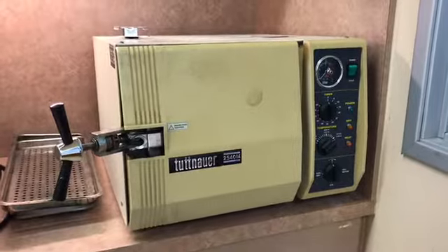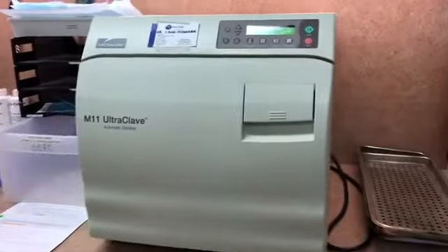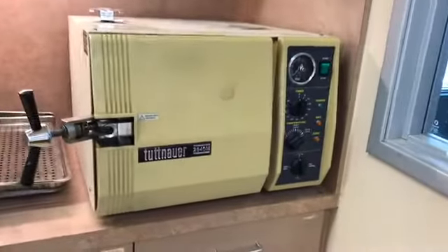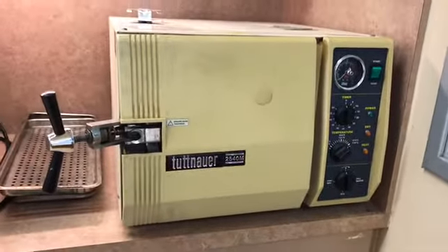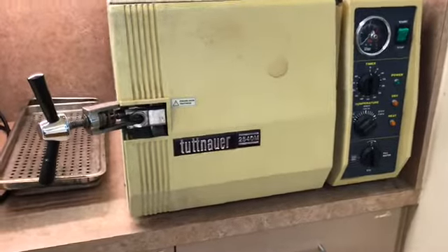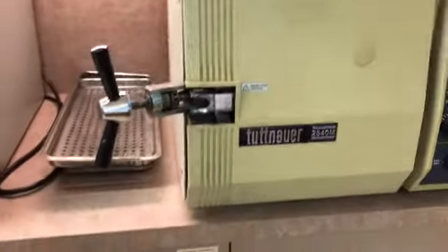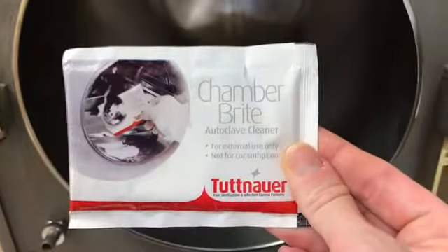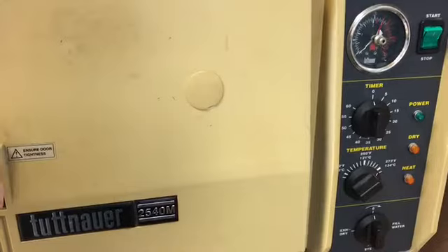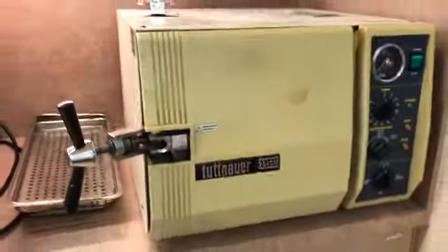So this is another type of autoclave that we have. This is the one I just packed, and this is just an older version. To maintain the autoclaves, they are cleaned daily just by wiping down the outside with a wet cloth, but we clean them monthly. So what we would do is we remove the trays, take this cleaner and its powder, and sprinkle it along the bottom here, and then we would close it and run a cycle. That's how you maintain an autoclave.